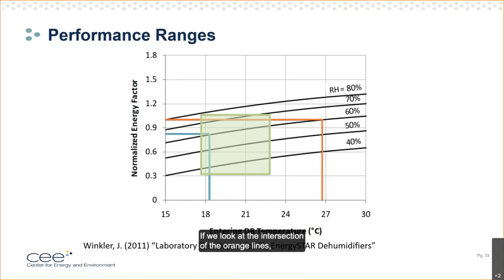So if we look at the intersection of the orange lines, that's at 80 Fahrenheit and 60% relative humidity. They found that, in fact, they have a normalized energy factor of 1. They were meeting their performance expectations. But you can see that as it gets drier, normalized energy factor falls. As it gets cooler, normalized energy factor falls. Remember, drier air enters these units and they remove less moisture.